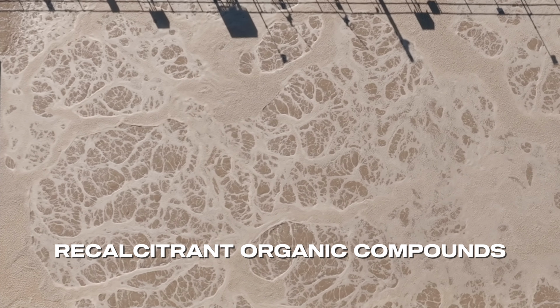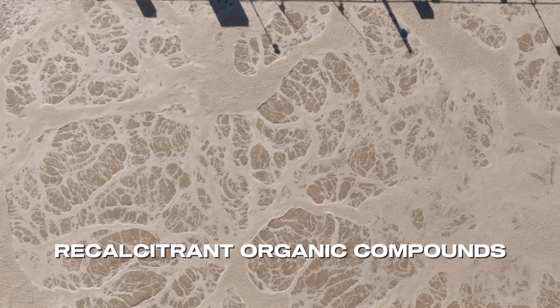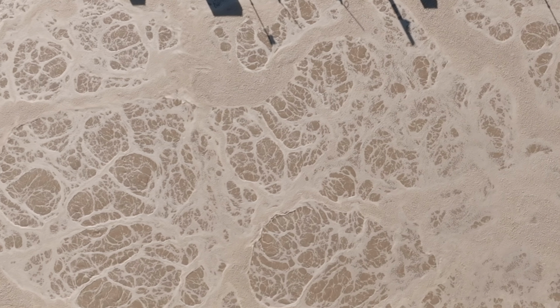Some organic compounds are recalcitrant, which means that they are resistant to biological treatment and slow to degrade. A high COD to BOD ratio is often a warning sign. And there are surfactants, which reduce surface tension, produce foaming, and interfere with separation processes like flotation and settling. If left unchecked, they can seriously impact performance across the entire system.